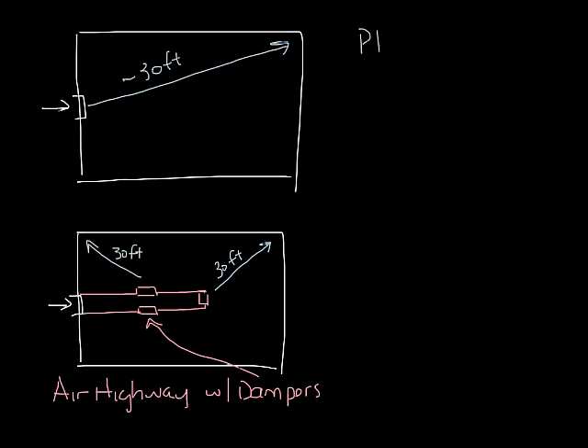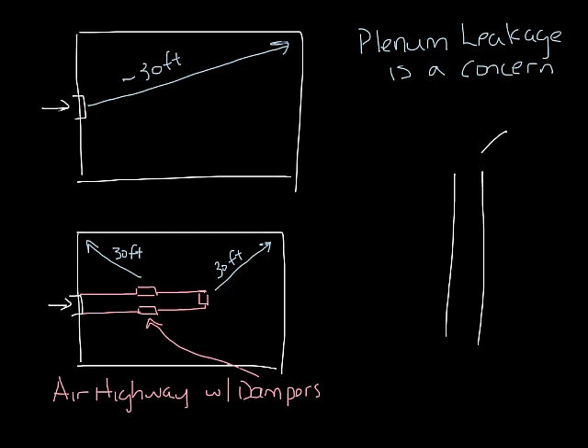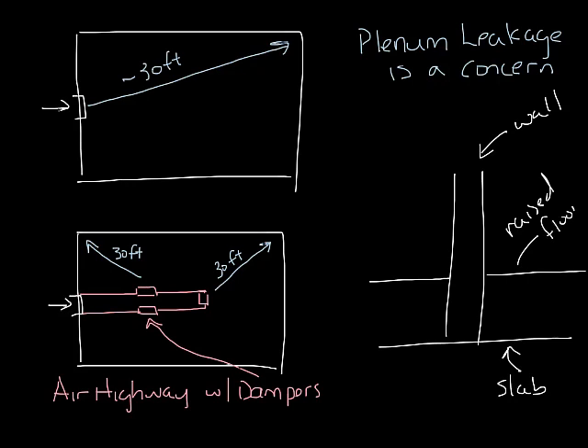Air leakage from the plenum is a very important consideration as well. On the room side of the raised floor, the carpet tiles will help seal the plenum, and any leakage will go into the occupied space, so it's not as big an issue. A bigger concern is sealing any wall penetrations in the plenum space so that supply air doesn't leak into the space between the walls, which is a waste of energy.